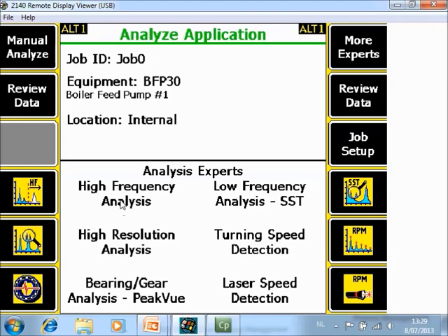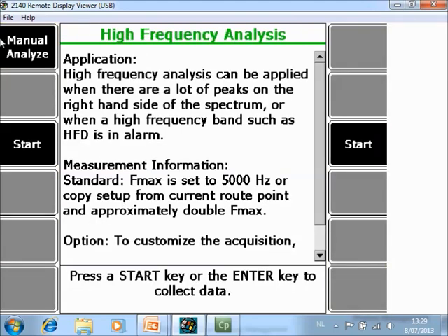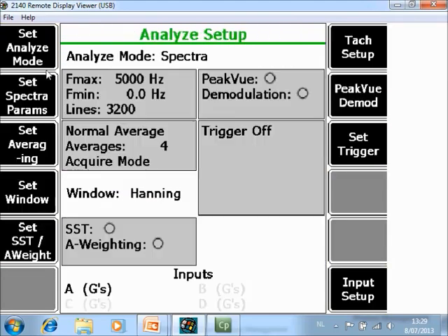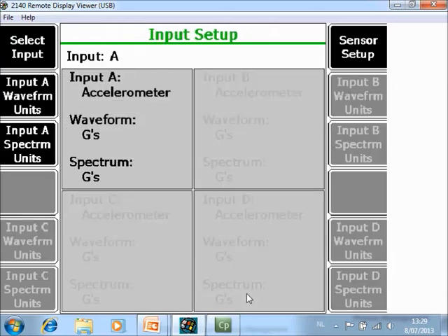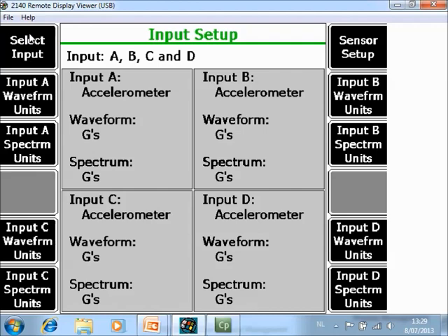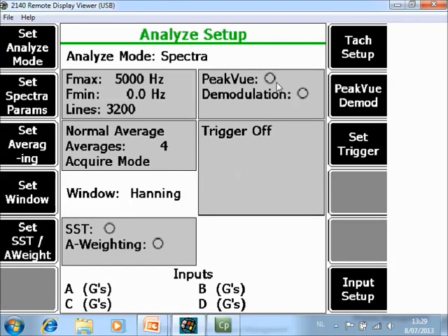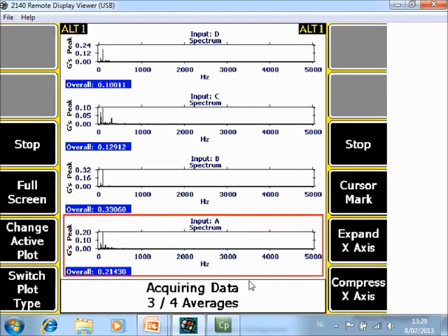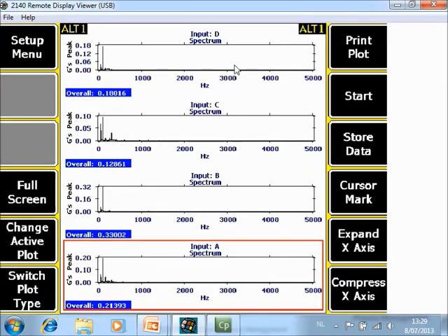If I go back to High Frequency Analysis, but now go to Manual Analyze, I can also activate more inputs with F12 and F1 Select Input. I activate B, C, and D channels. Now I can also collect this data from 0 to 5000 Hz with 3200 resolution lines on 4 channels simultaneously. This data can also be stored in the job mode.